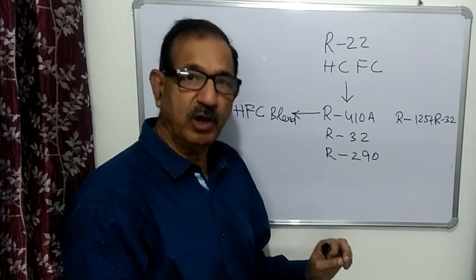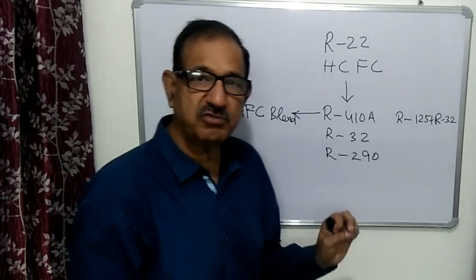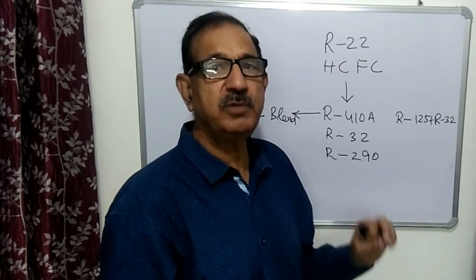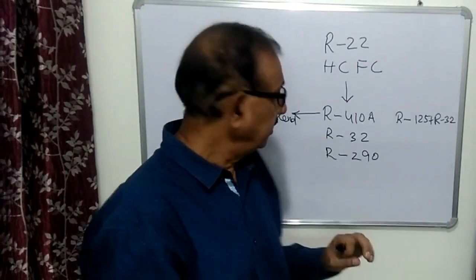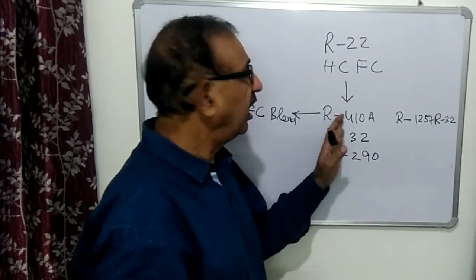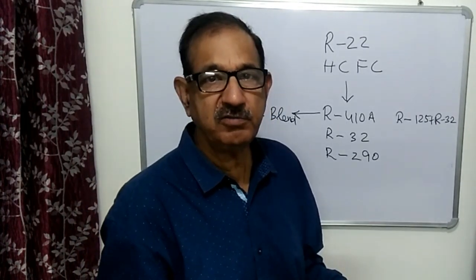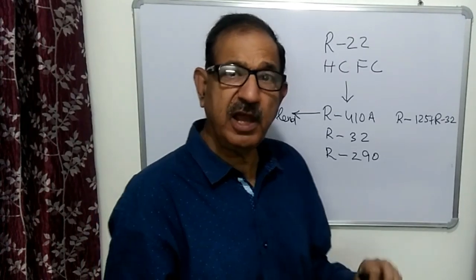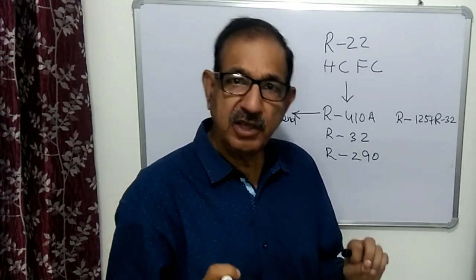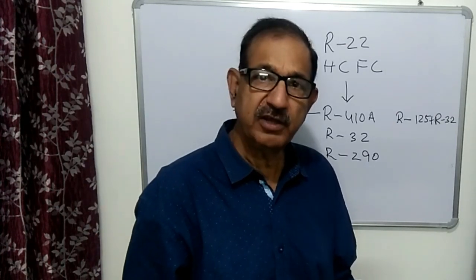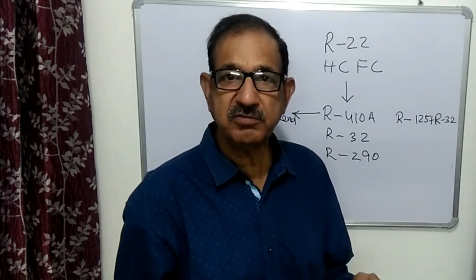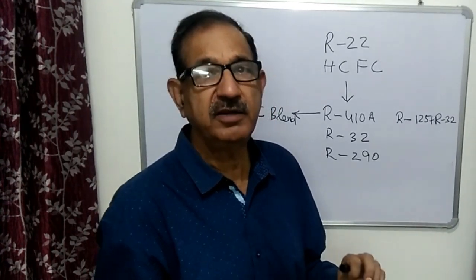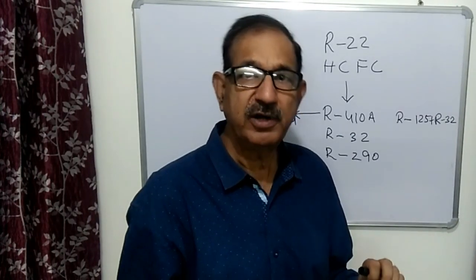R125 and R32 both have different boiling temperatures, so whenever you charge this refrigerant, please charge it in the liquid state — keep the cylinder upside down. R410A is a very high-pressure refrigerant, and you must use only the recommended gauge manifold, which has a low-side gauge of 500 psig and a high-side gauge of 800 psig, meant for R410A.